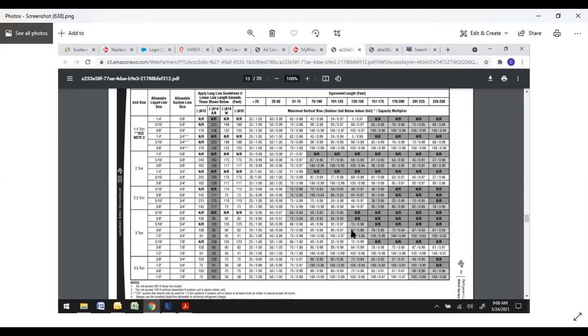You'll see this kind of a darker shaded gray line. The further you go, you'll see this 0.96, 0.95. You start going down, you'll start losing capacity. So in this case here, 3/8, 3/4, you're pretty much fine with very little loss up to 125 feet. But as soon as you cross over that, you start losing capacity. If you see this darker shaded gray where it says NR, once you cross into this line, then you're kind of on your own. It's not recommended and it's not really rated, so it may work, it may not, but as long as you follow these guidelines, you'll be okay.